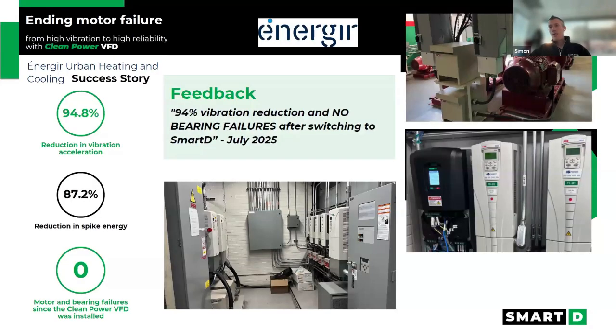And we also observe that in the field. This is a case where we were approached by a customer that was having recurring bearing failures. And they really tried everything. They had chokes, they had dV/dt filters, they tried replacing the motor, and nonetheless, they kept on having those bearing failures. They then installed the SmartD Clean Power VFD, and they got a new vibration analysis. So they really had a picture before and after. And that vibration analysis gave a complete new story where nearly 95% of the vibration acceleration was gone. The spike energy, nearly 90% of that was gone.